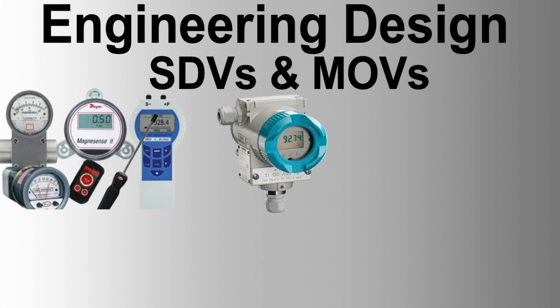Actuator torque. The torque available from the actuator at any point in the stroke shall be a minimum of 2.5 times the valve torque required to operate a new valve for both the spring closing and externally powered opening, or vice versa for fail-open applications, strokes, including breakaway with the valve under maximum differential pressure and at maximum operating pressure.